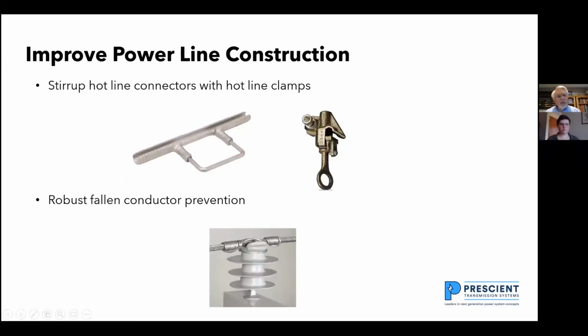When I talk about improved power line construction, I see a lot of things we could do to improve power line construction. For example, I see people putting hot line clamps directly on a power line. If the hot line clamp works free and causes a hot spot and damages the conductor, it can fall down and go on the ground. There's a high probability that would ignite a wildfire.